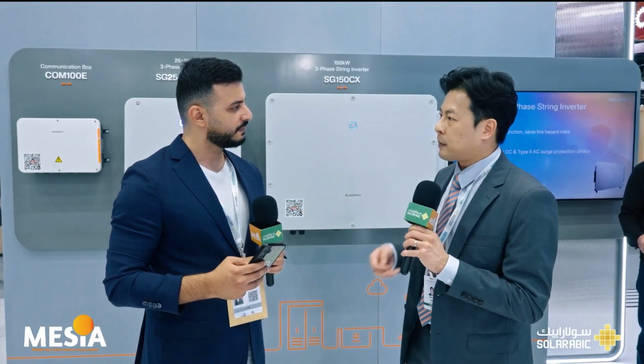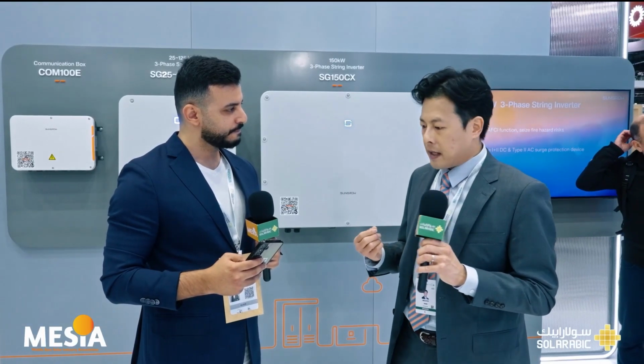If we're using this new technology, we are capable of providing 100% of the unbalanced single phase faults and supplying it at the same time as well. The third one is the magnetizing inrush as well. As we were just saying, the new Power Titan series has the capability of overloading at 150% for 10 seconds. This attribute is so critical in terms of providing the inrush current to the system. That means you can allow for more inrush current in the system. If you don't have this, it will usually cause the tripping of the protection system as well. So this is actually very, very critical.